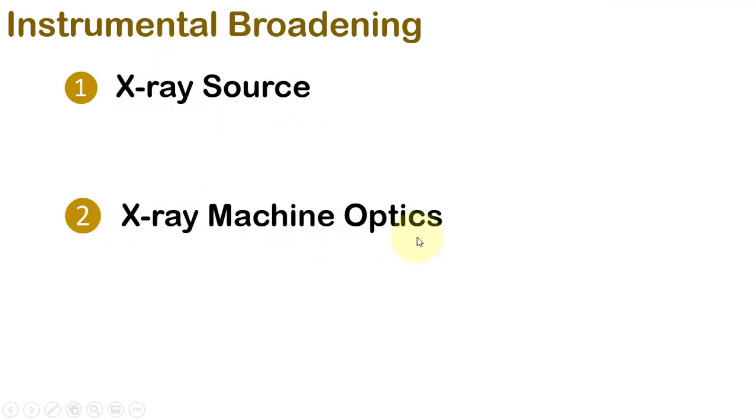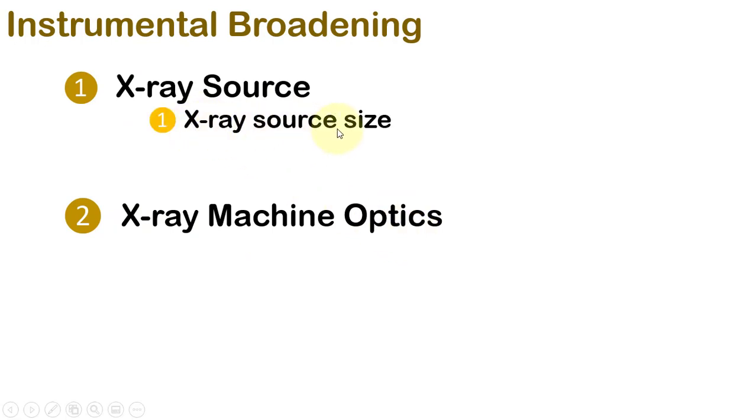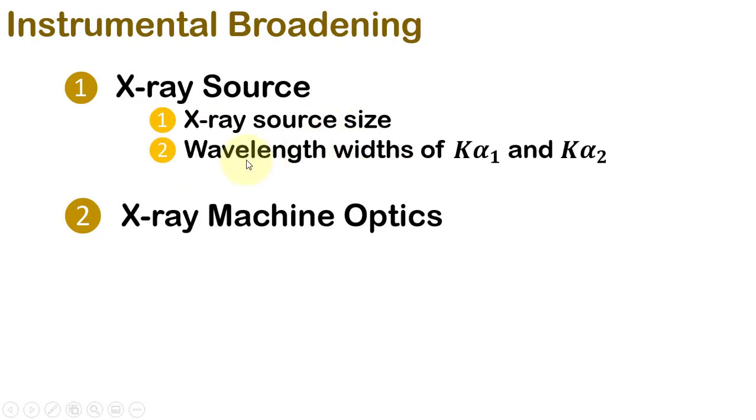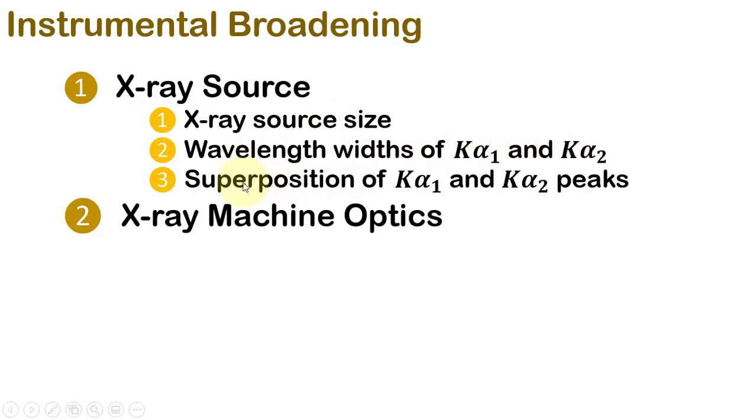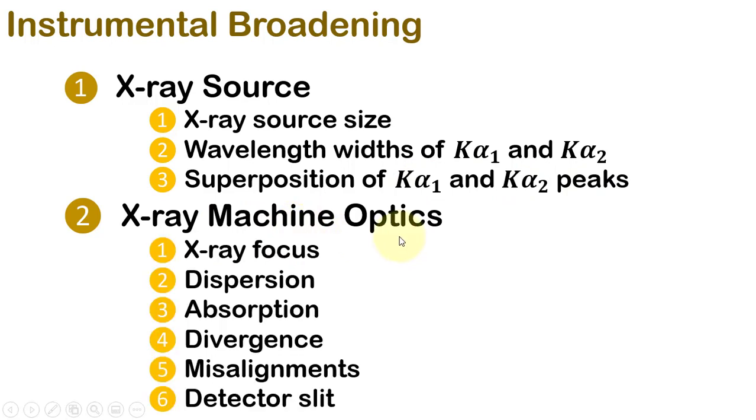In the instrumental broadening, the two major components are the X-ray source and the X-ray machine optics. In the X-ray source, broadening is caused by the size of the X-ray source, the wavelength widths of Kα1 and Kα2 lines and the superposition of Kα1 and Kα2 peaks. While in the X-ray machine optics, some of the factors are these.